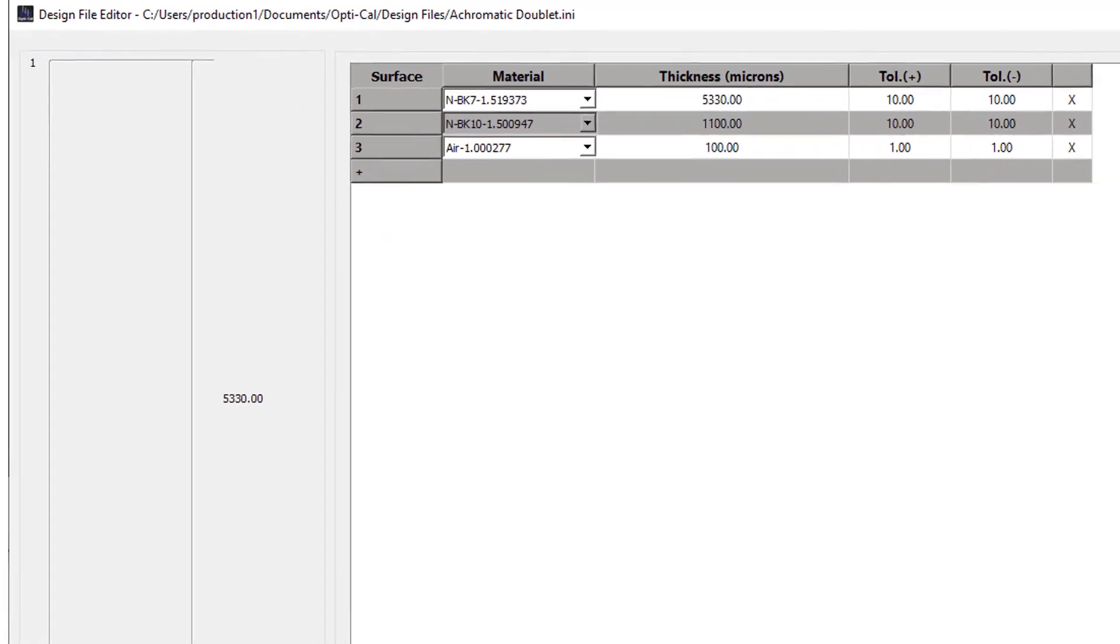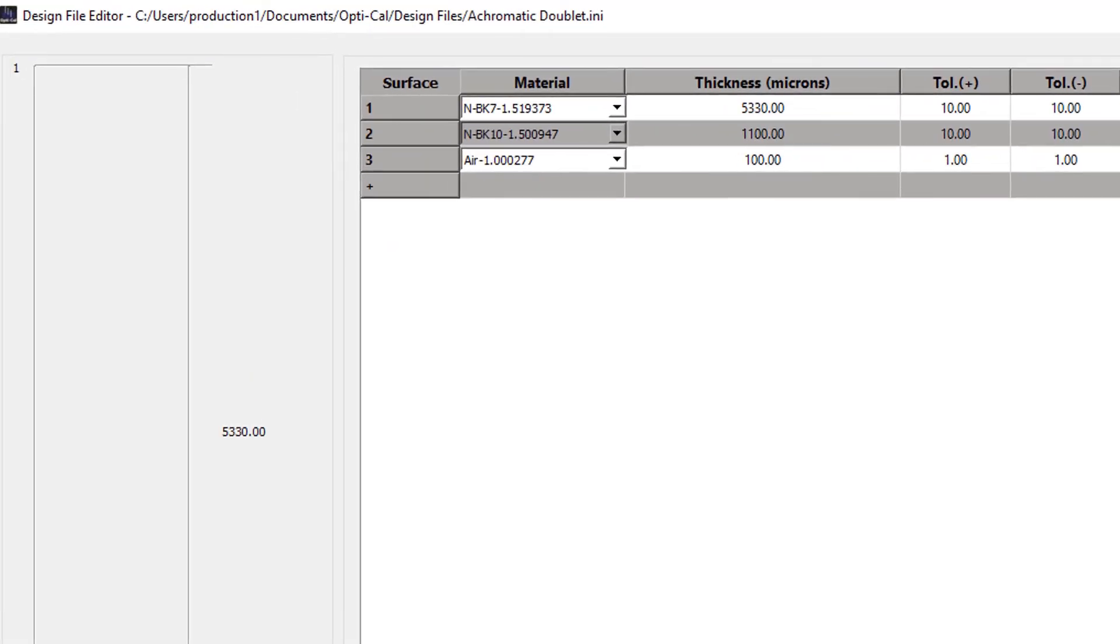The quality control mode allows for unlimited part numbers to be pre-entered into OptiCal with design thicknesses and tolerances. This simplifies measurement by production and quality control personnel.